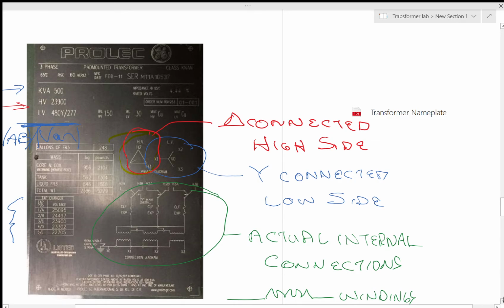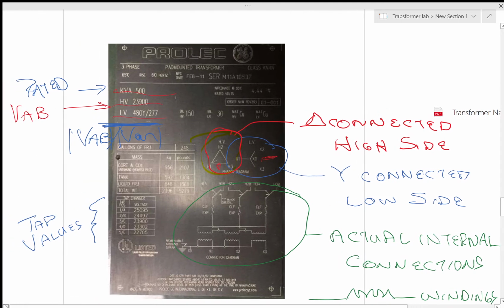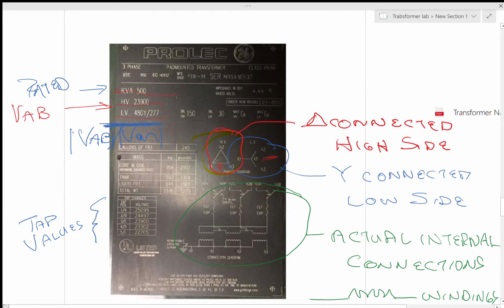It tells you the kVA rating. It tells you the high side voltage. It tells you the low side voltage. It tells you how the high side is connected, delta. It tells you how the low side is connected, Y connected. It tells you how it's connected internally, right here, the actual internal connections and how you see them in there. Here is the tap changer values. Let me slide this over a little bit so you can see that a little better. There's the tap changing values.